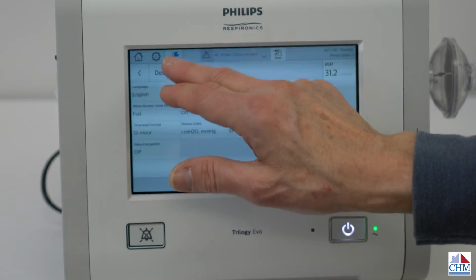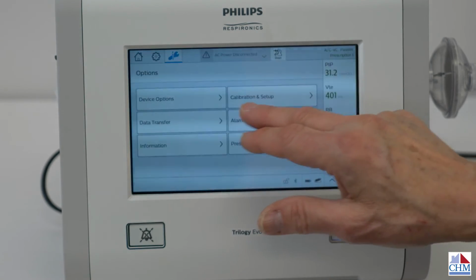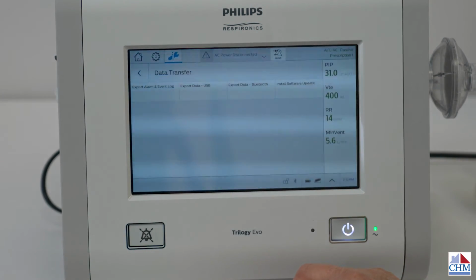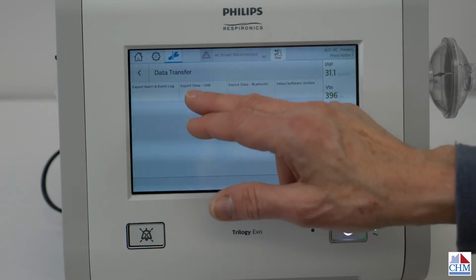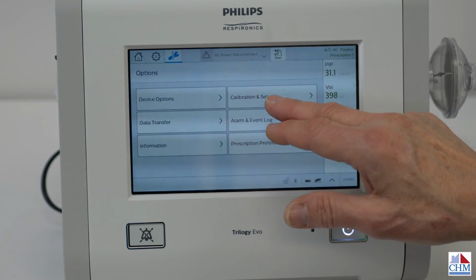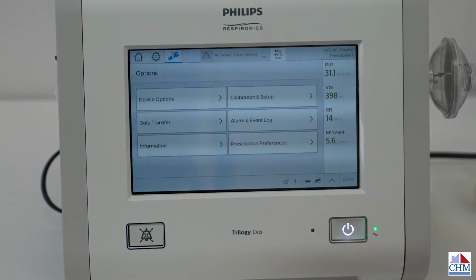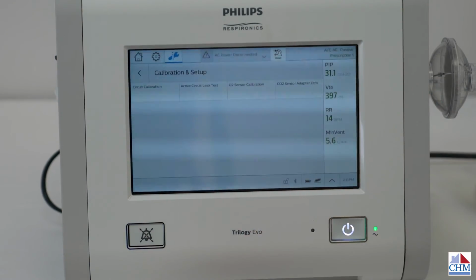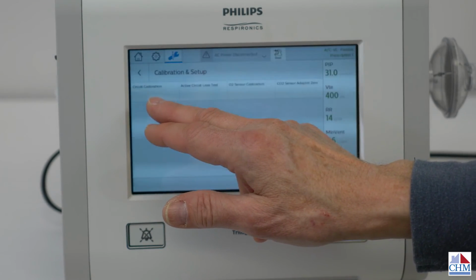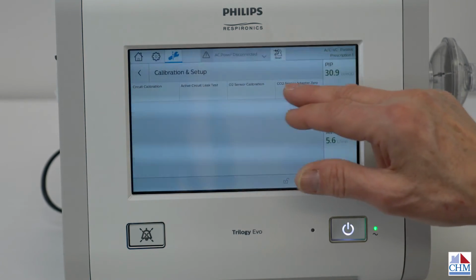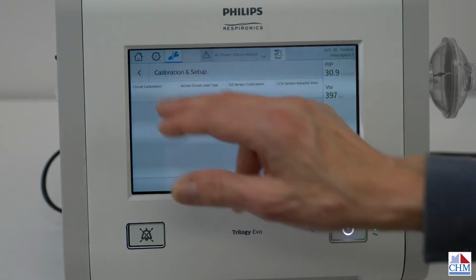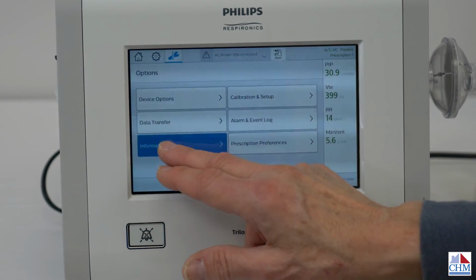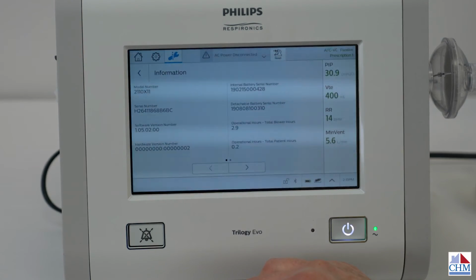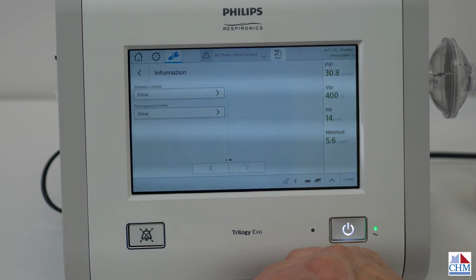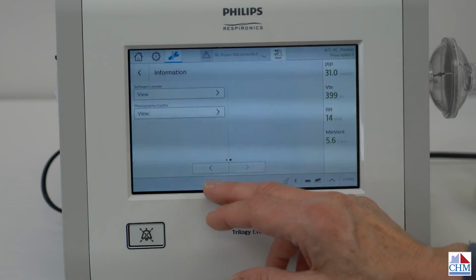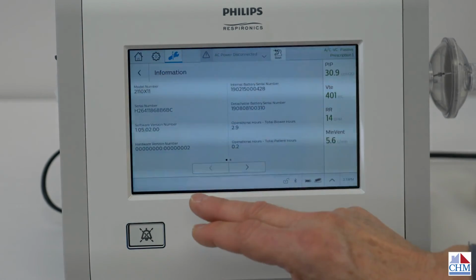And we'll go back into this screen. And some other options. We've got data transfer, if we need to export data to a USB or different options like that, which isn't used real often, but usually we are using the Bluetooth and being able to get data off of Care Orchestrator. Calibration and setup, we can go in here and we can calibrate our circuit, whether it's a passive circuit or an active circuit, and CO2 and oxygen sensors too, if they're used. And then we've got information. This is just information on the ventilator. This is where we would go to be able to find the serial number and software numbers and that kind of thing. And also add a photograph and that kind of thing for the background of the unit.